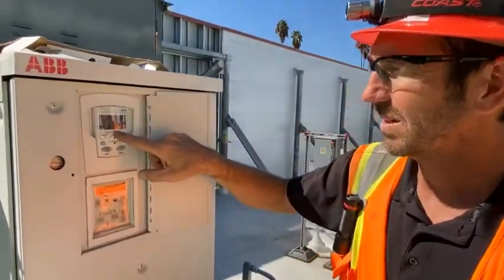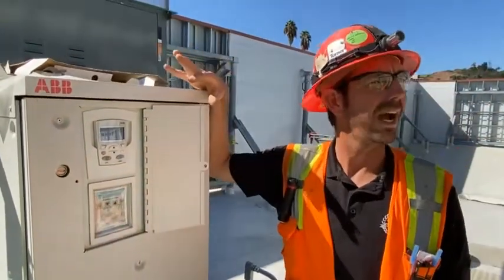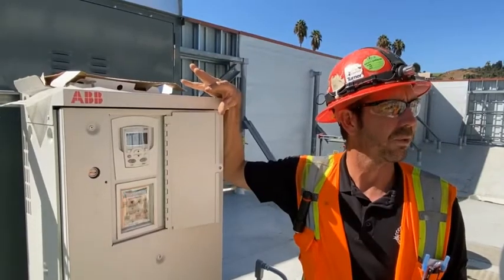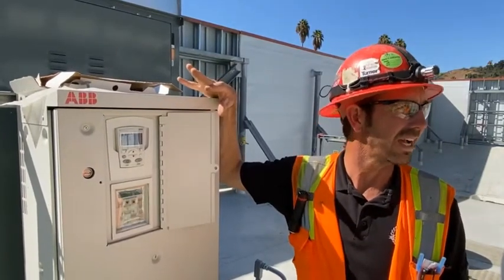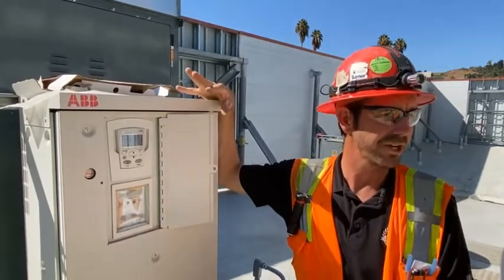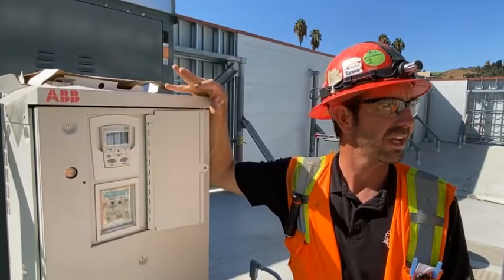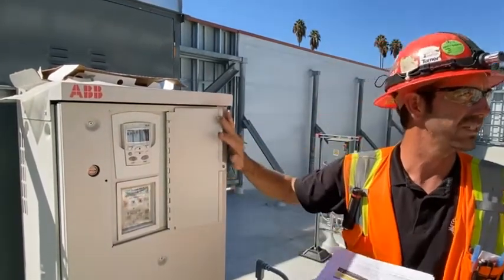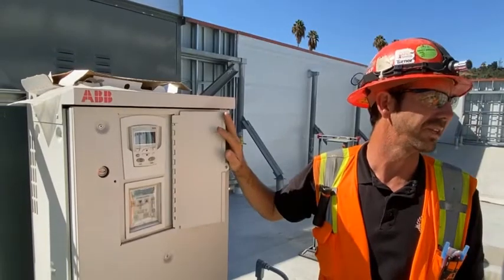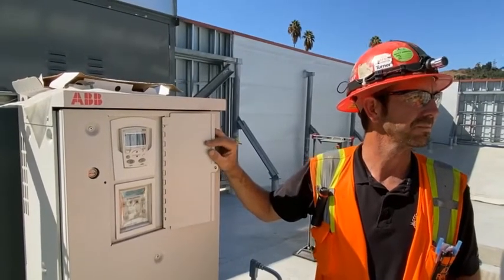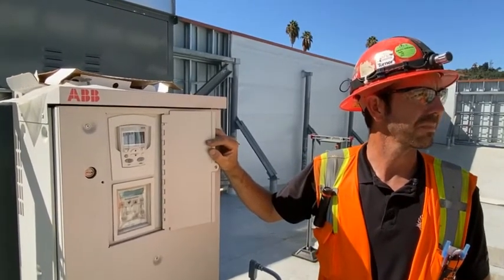What determined the speed? Our balance guys that we hired calculated the CFM, or the engineers calculated the CFM. The balance guys took all those readings and measured all the readings downstairs at the hoods and determined what speed this unit needs to run to give us those CFMs at the hood. Okay, so there's no control, there's no sensor controlling it.